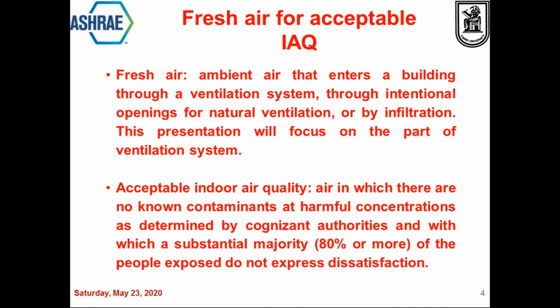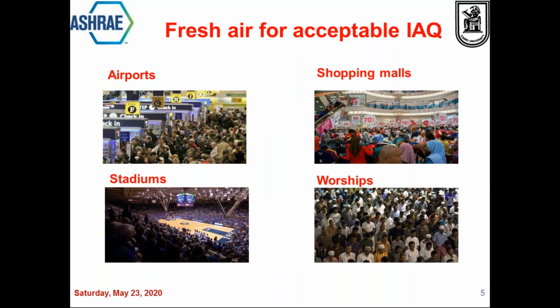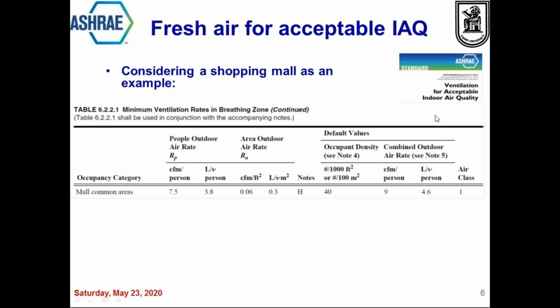So fresh air is one of the important parameters that we should have in buildings during ventilation, especially since not in every case can we use natural ventilation. The acceptable indoor air quality requires that the air should be clean and at a temperature that provides thermal comfort. Examples of places where fresh air is needed for acceptable indoor air quality are airports, shopping malls, stadiums, places of worship, churches, synagogues, temples, etc. In these applications, we expect to have a large number of audience, and consequently, as per ASHRAE, very large amounts of fresh air requirements.